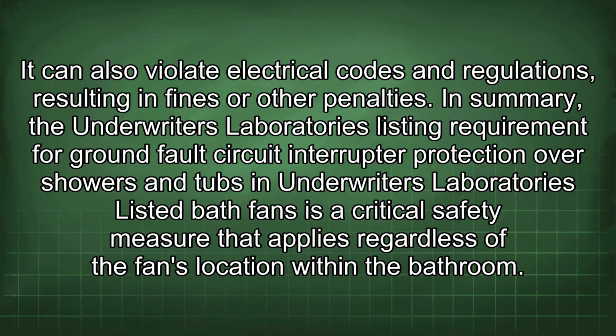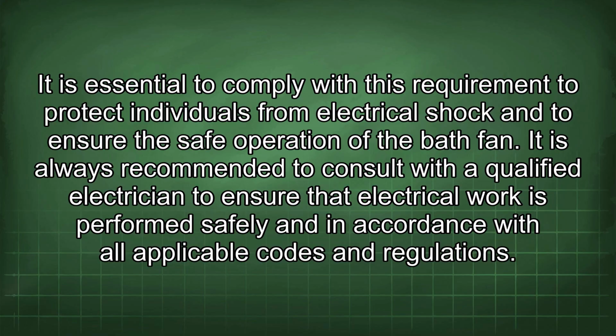In summary, the Underwriters Laboratories listing requirement for ground fault circuit interrupter protection over showers and tubs in Underwriters Laboratories listed bath fans is a critical safety measure that applies regardless of the fan's location within the bathroom. It is essential to comply with this requirement to protect individuals from electrical shock and to ensure the safe operation of the bath fan. It is always recommended to consult with a qualified electrician to ensure that electrical work is performed safely and in accordance with all applicable codes and regulations.